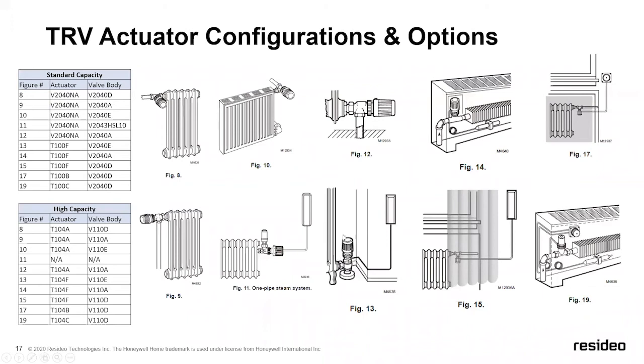If your actuator's vertical, the heat is going to rise up because we're using very convective heat with this. It's going to rise up and it's not going to give you the correct reading here. So if you'll look, here's one that maybe there was no other option. Maybe this is what was here.